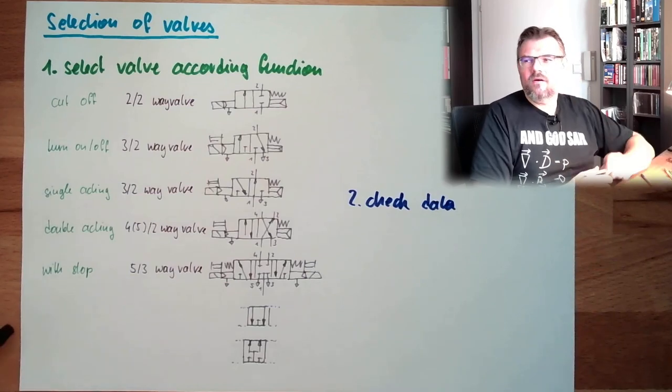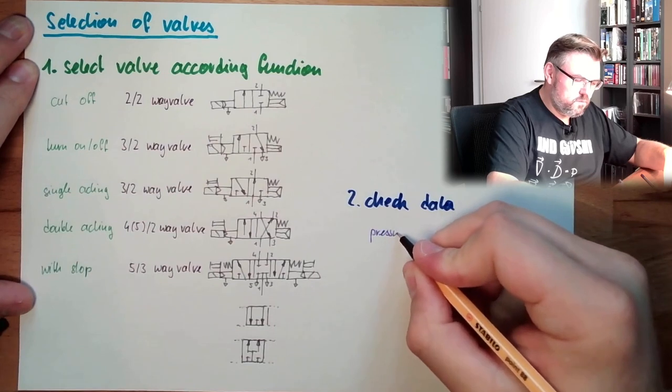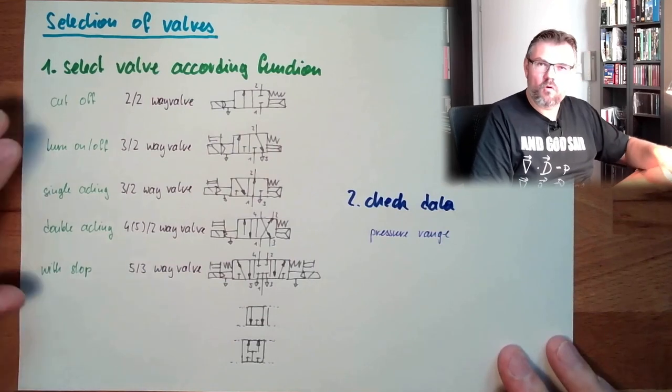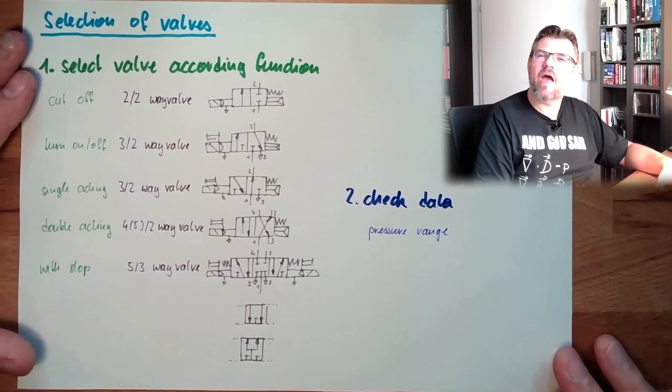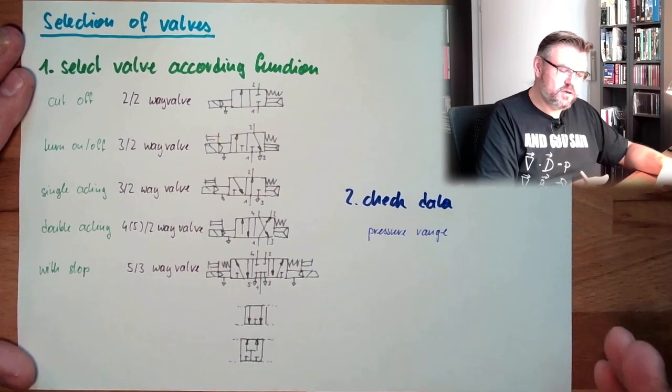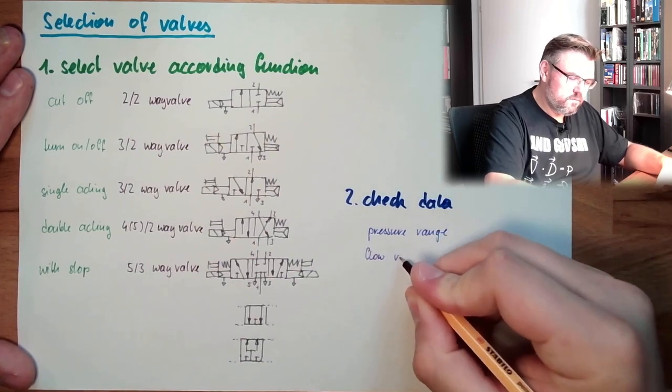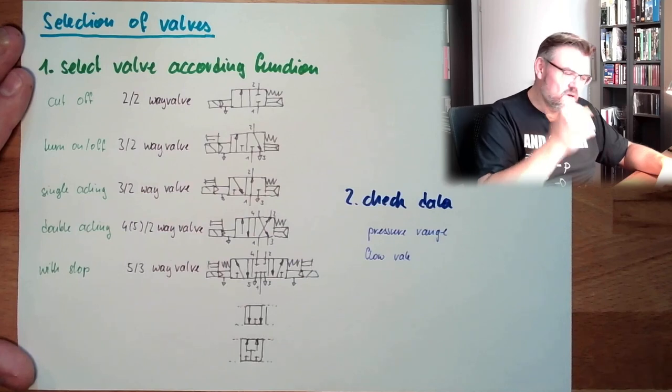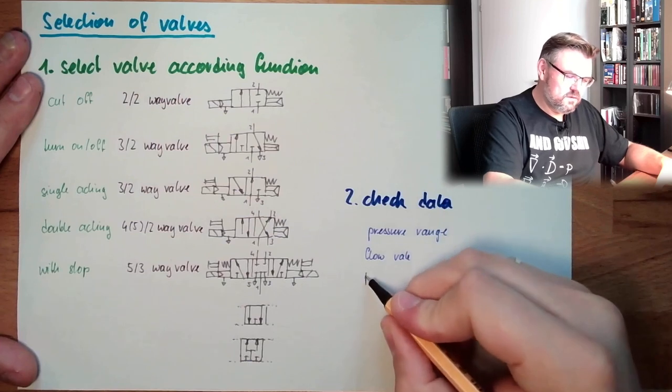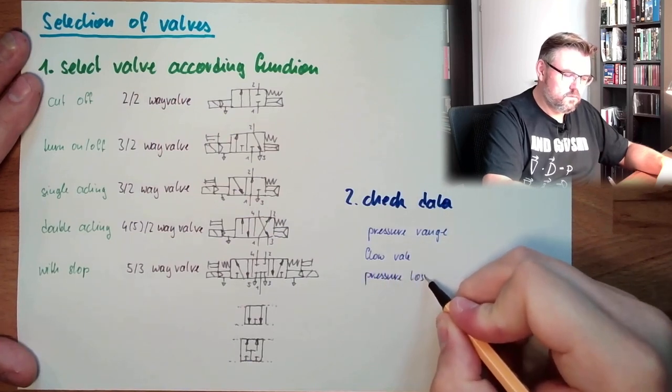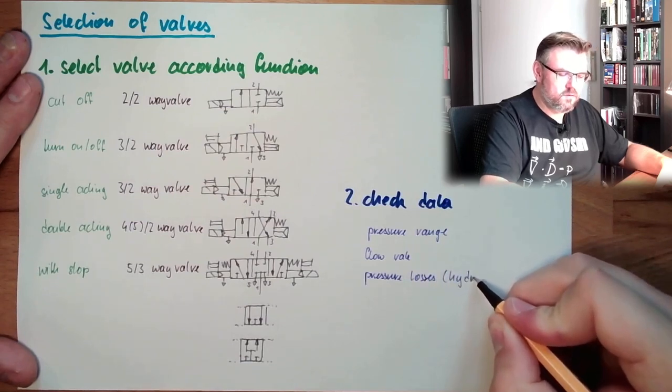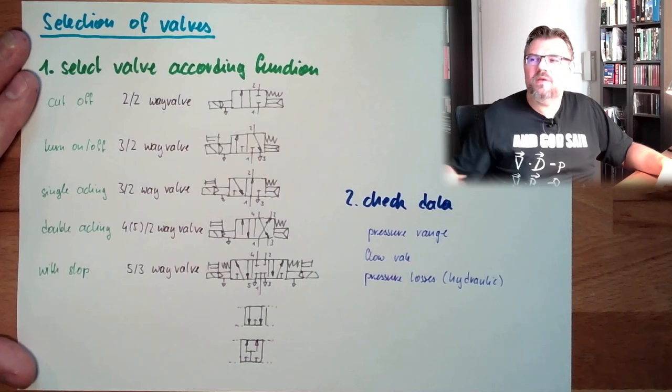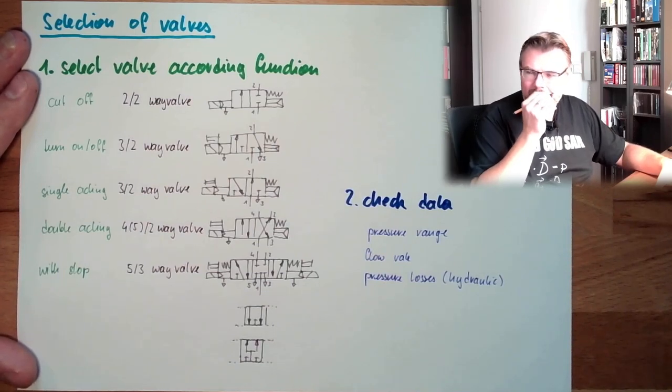So we do have things like pressure. Pressure range needs to fit the pressure, especially in hydraulic valves. If you have extraordinary high pressures, then you might run into troubles there. Pressure range needs to fit. Then the flow rate. Flow rate, how many liters per second can pass there? And in hydraulic valves also the pressure losses. This is mainly on the hydraulic side. These are things which need to be considered, switching times.